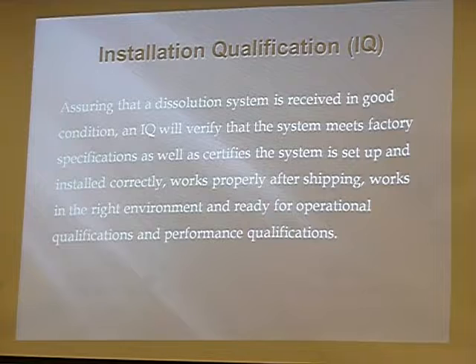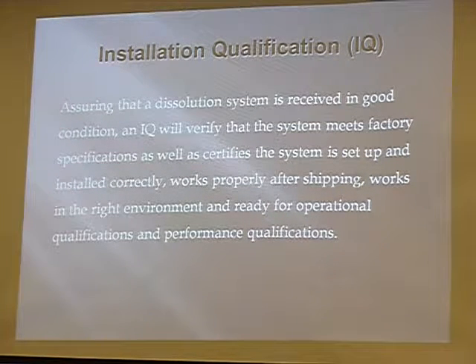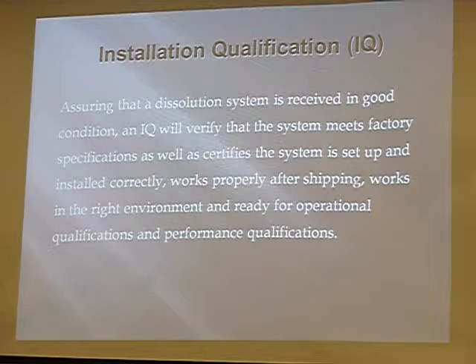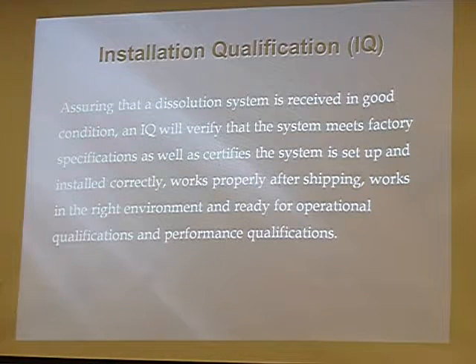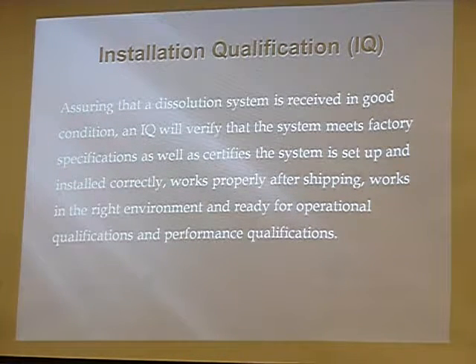The installation qualification, the IQ section. I gave you guys all one of them for whatever systems you guys all have. Ensuring that a dissolution system is received in good condition. The IQ will verify the system meets factory specifications, as well as certifies the system is set up and installed correctly, works properly after shipping, works in the right environment, is ready for operational qualifications and performance qualifications.